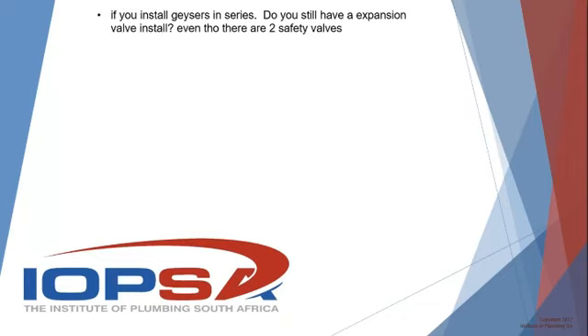This is another strange question. If you install geysers in series, do you still have an expansion valve, even though there are two safety valves? Does somebody want to just explain the difference in pressure ratings and opening pressures between the safety valve and expansion valve, perhaps? Okay, your safety valve is rated at 1.5 times the rating. So if it's a 400 kPa, it would actually only open up for pressure at 600 plus minus 10%. So you're looking at between 540 and 660. Whereas now, if it's your relief valve, it opens up at 100%. So that is 400 kPa. And if your geyser is 400, that's what you're going to have in.